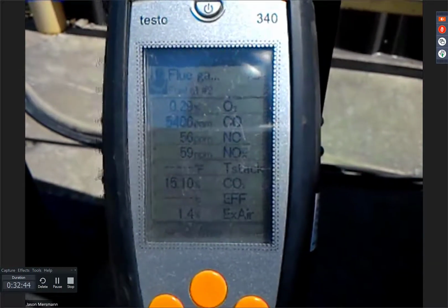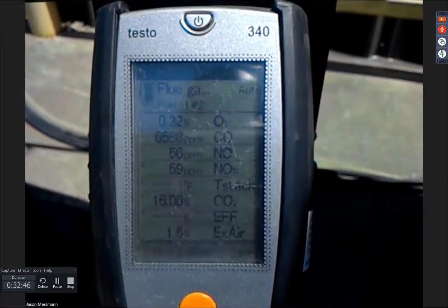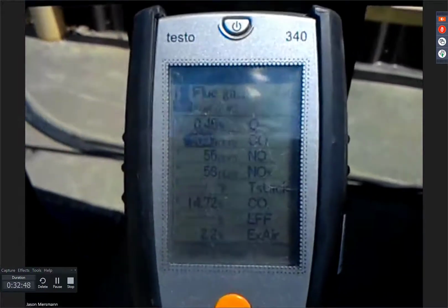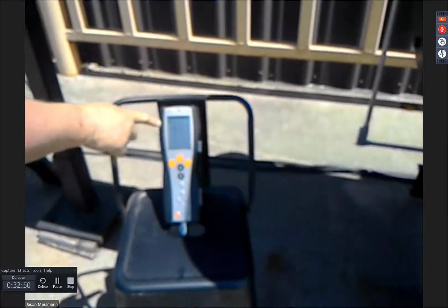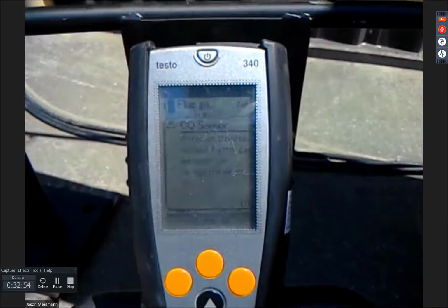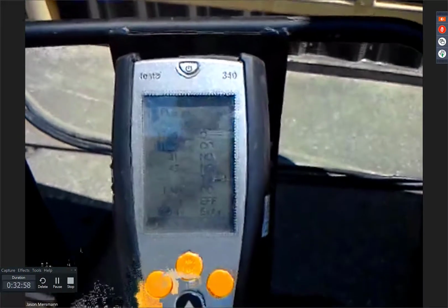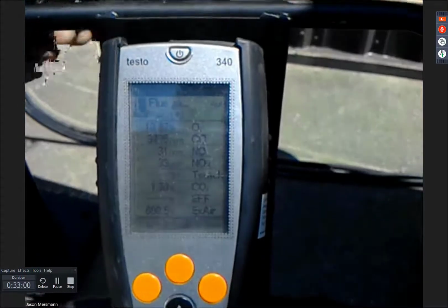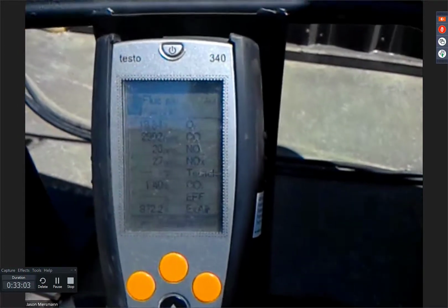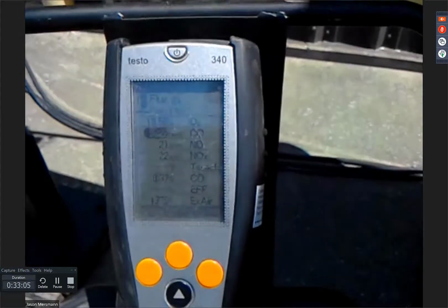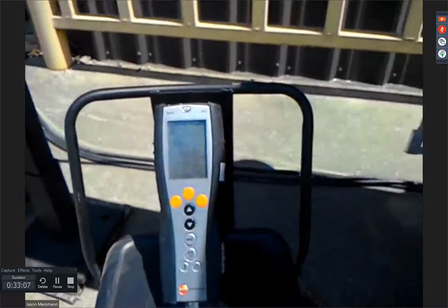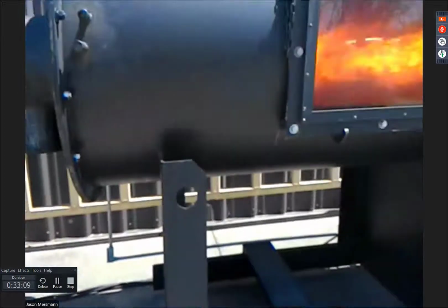So now, Kevin, why don't you go ahead and make a flame that's good? So you guys also see that the O2, yeah, go ahead and pull it. You also see that the O2 is 0.6. It's really, really low. And you actually see the warning sign on that because it's an overly saturated CO monitor. So now, Kevin, go ahead and make it a good flame, while I go and talk about some of the details.